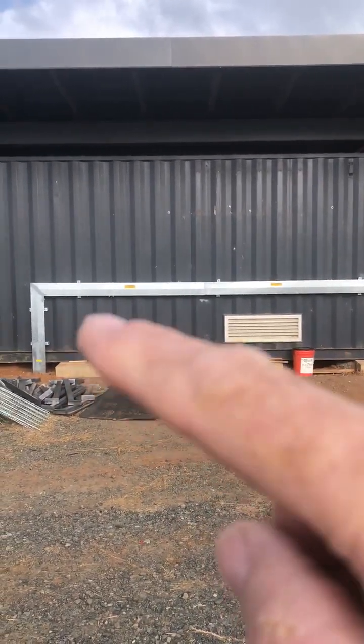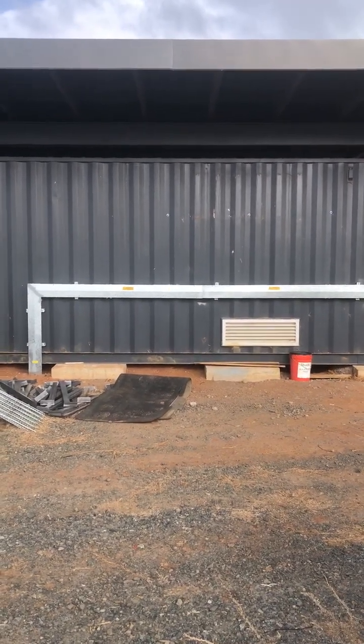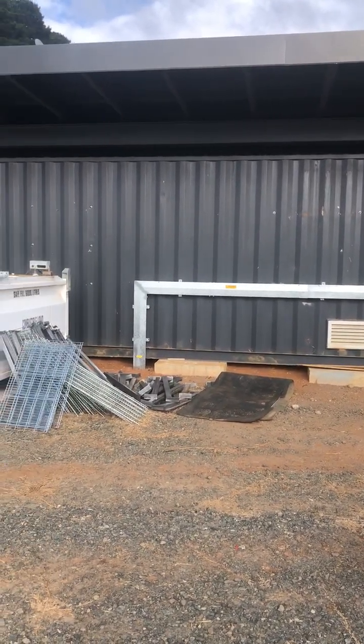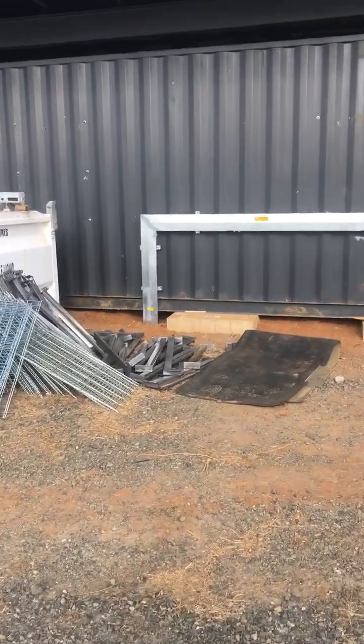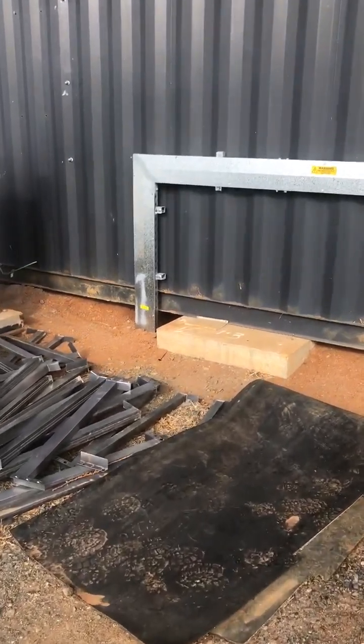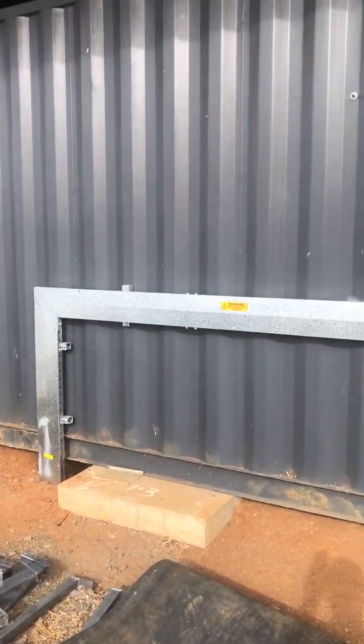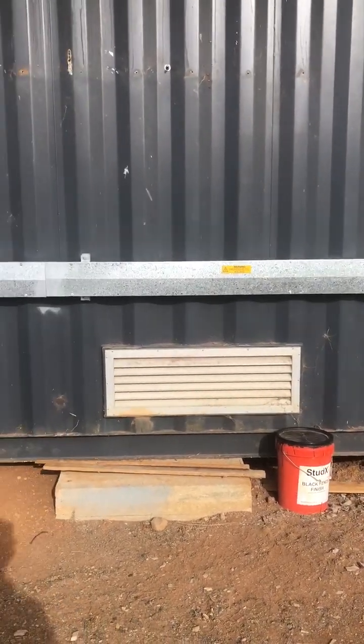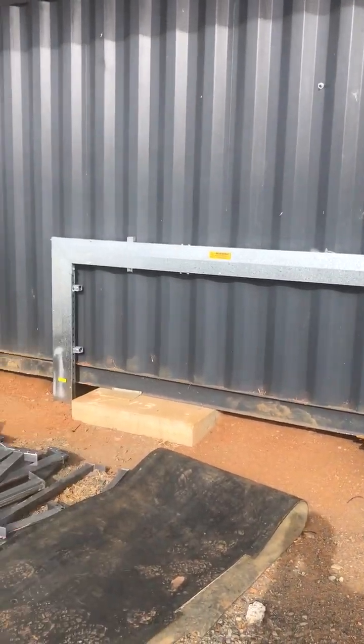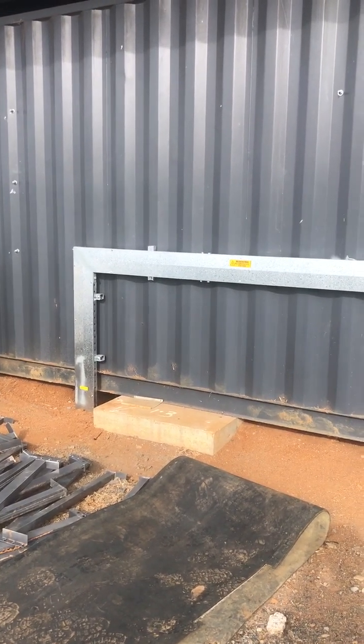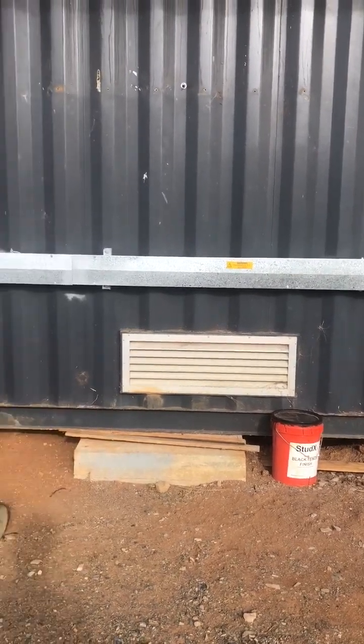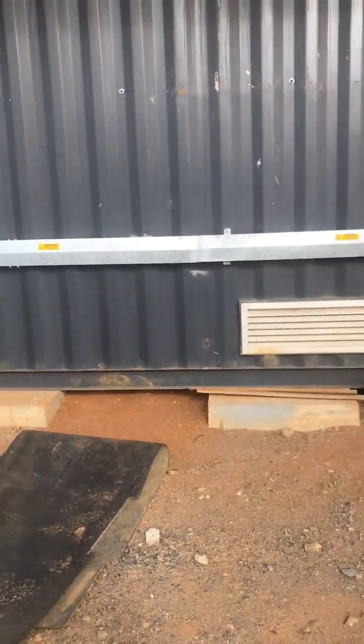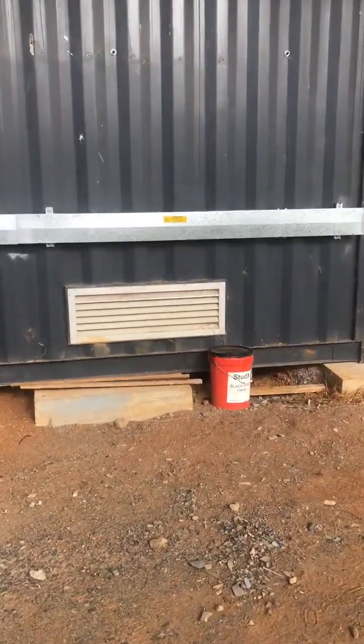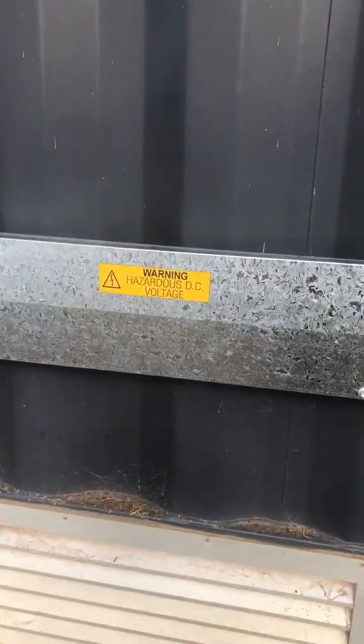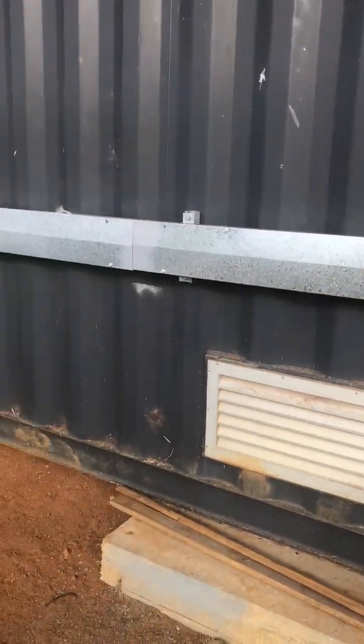You'll notice there's a cable ladder, and that's the cables that come up from the array that I just showed you. They come up underground in conduits, come up into the cable ladder, and then into the inverters, which are inside, which I'll show you in a minute. It's very important to protect string cables, because in this case the voltage is up over 800 volts, which can be quite hazardous. So it's very important to provide signage on equipment like this, and also to keep it protected so it can't be damaged.